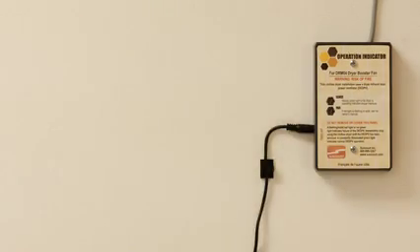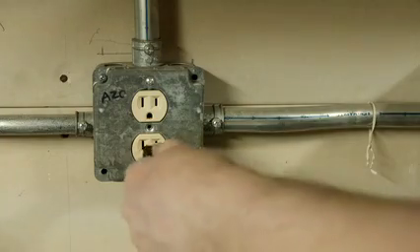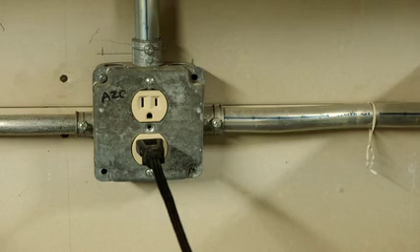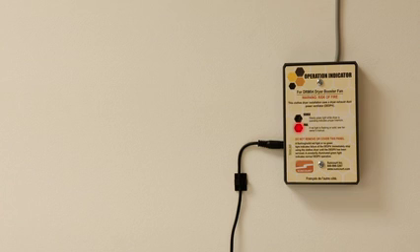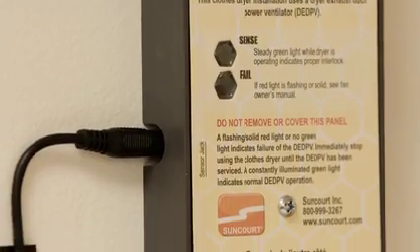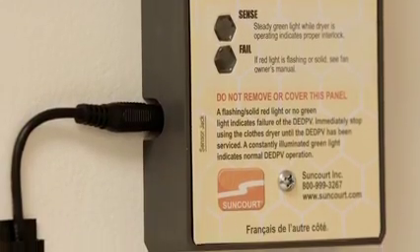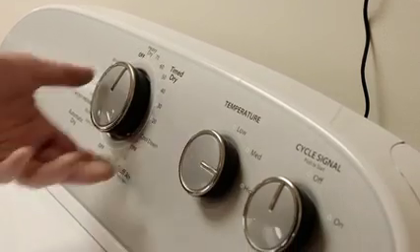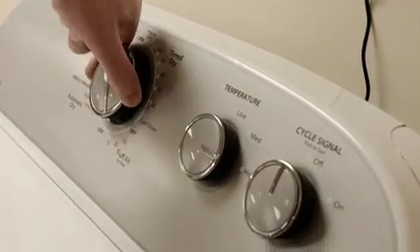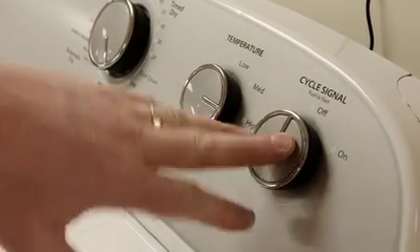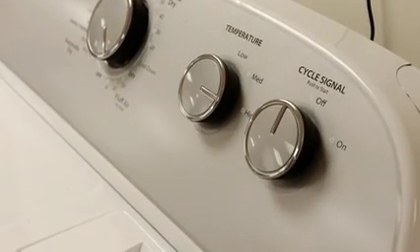Now apply power to the DRM04 for the first time. If the red fail light is lit solid on the indicator, make sure the plug from the current sensor wire is fully seated into the jack. To test the interlock, set the dryer to an air fluff, no heat cycle, and start the dryer.